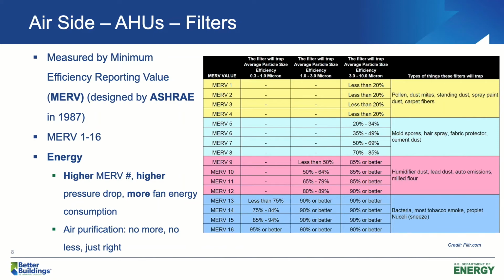Air filters. We need air filters to clean and purify the air. We typically use minimum efficiency reporting value, also known as MERV, to indicate the efficiency of filters. MERV was designed by ASHRAE in 1987. The value of MERV ranges from 1 to 16. The higher the MERV value is, the cleaner air we will get. However, it also means more pressure loss across the filters. We will need to use more fan energy.